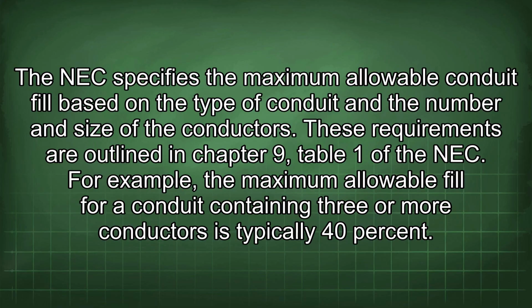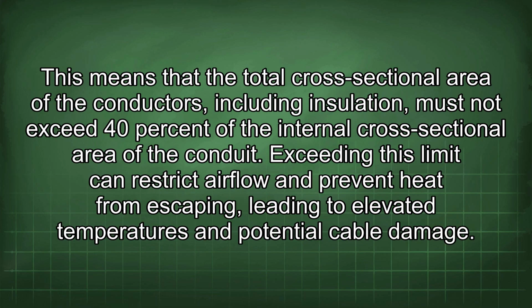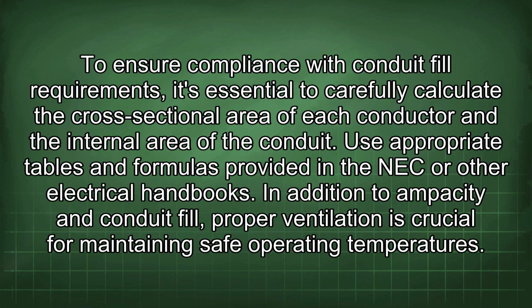For example, the maximum allowable fill for a conduit containing 3 or more conductors is typically 40%. This means that the total cross-sectional area of the conductors, including insulation, must not exceed 40% of the internal cross-sectional area of the conduit. Exceeding this limit can restrict airflow and prevent heat from escaping, leading to elevated temperatures and potential cable damage. To ensure compliance with conduit fill requirements, it's essential to carefully calculate the cross-sectional area of each conductor and the internal area of the conduit. Use appropriate tables and formulas provided in the NEC or other electrical handbooks.